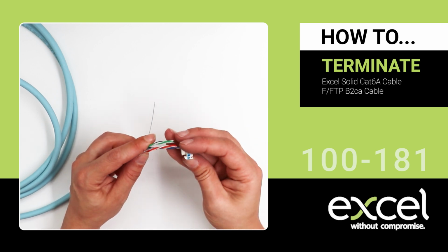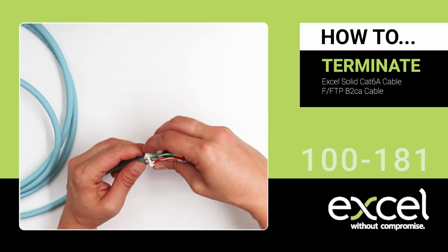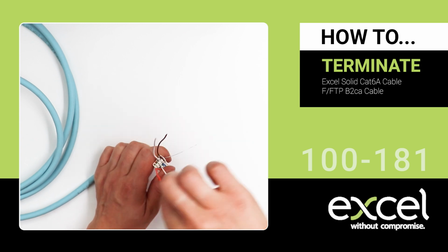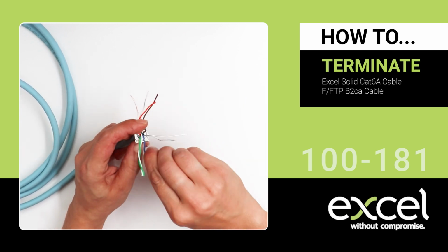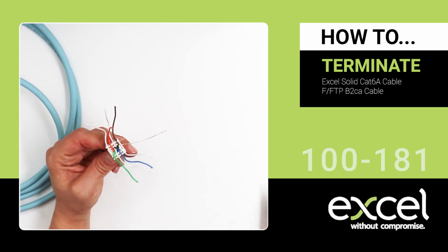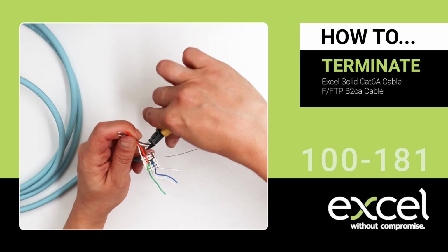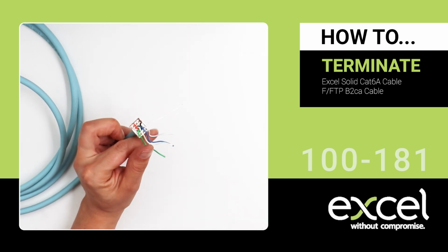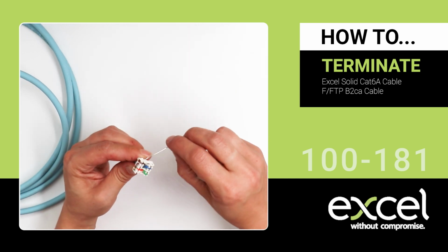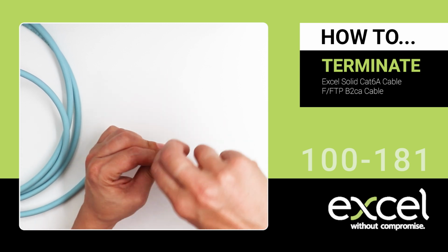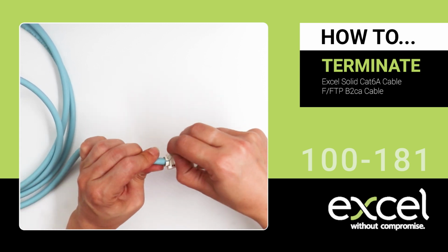Insert the cable through the termination cap, then untwist and fan out the pairs. Following the colour code on the cap, insert the wires into their designated slots. Double check that the wires are in the correct position, then trim the excess. Wrap the drain wire 360 degrees around the base of the cap and trim any excess.